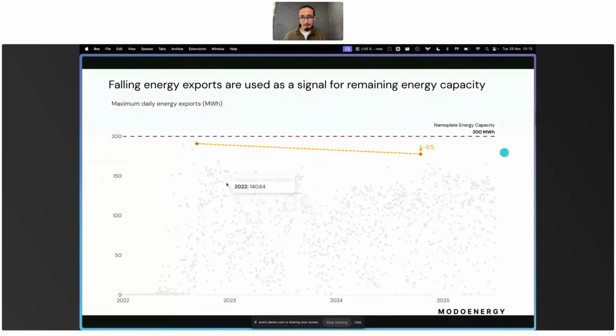What we then do is understand how this maximum energy export has decreased over time. We start with a reference point. This 200 megawatt hour battery exported 191 towards the start of its life. We track how many cycles it's completing as it goes through, and look for the second signal indicating what that maximum energy capacity is. After about 2 years, we see that its maximum energy export in the winter of 2024 was about 178 megawatt hours. So we're measuring a 6% drop between these two points, and the amount of cycles completed from point A to point B, which produces our chart at the start of the presentation.